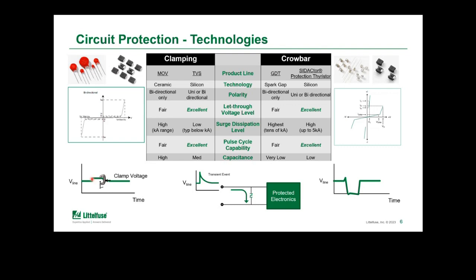So it holds the voltage level at a point that is above the operating voltage of the system, but ideally below the damage threshold of the circuit that you're trying to protect. And then once the transient dissipates, it will go back down to normal operating voltage levels. And here's an example of a VI curve for a typical clamping device. So you'll have very low leakage under normal operation, and then once you reach a breakdown voltage, you'll have a non-linear characteristic that will have very minimal change in voltage over a larger change in current. Examples of these types of devices are going to be metal oxide varistors or TVS diodes.